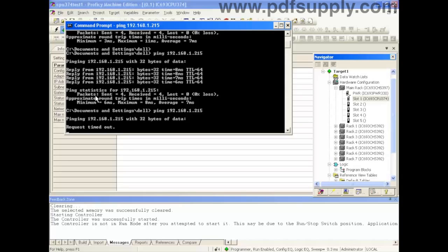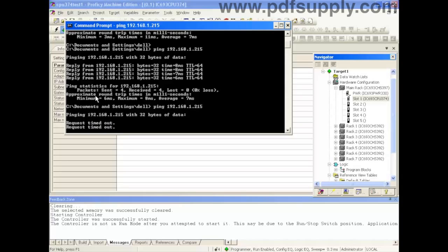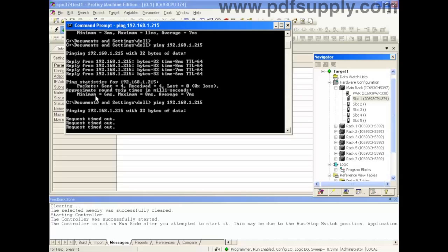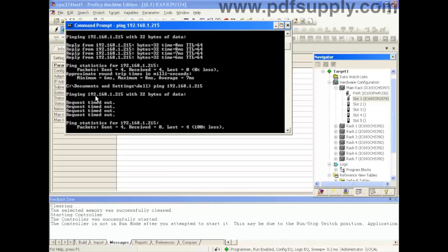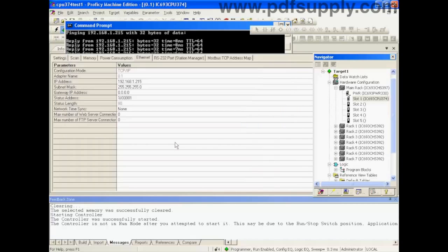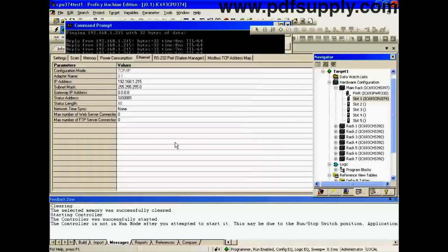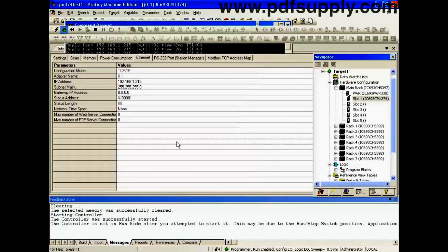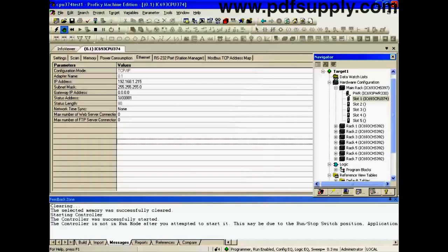The Ethernet's working fine. Next thing I would recommend doing, if you do think that you have a problem with your CPU 374, is let it run overnight, even let it run over a weekend. And what you want to do is when you come in the next morning or after the weekend, check to make sure that it's still in run mode, as you see here.